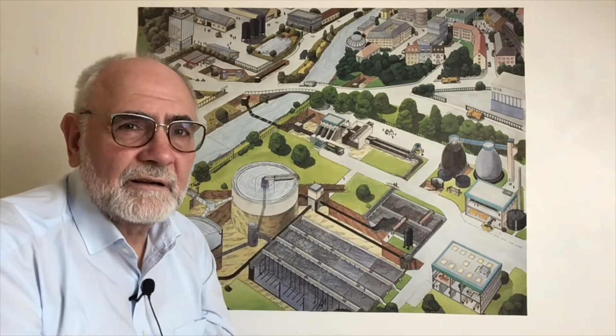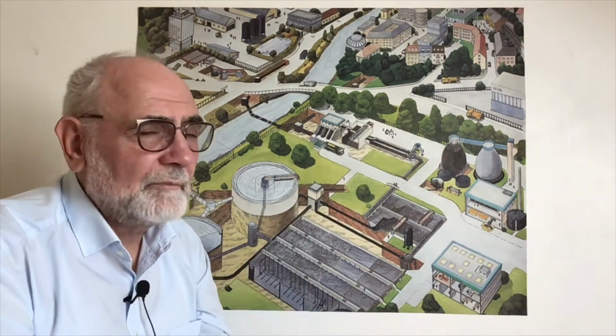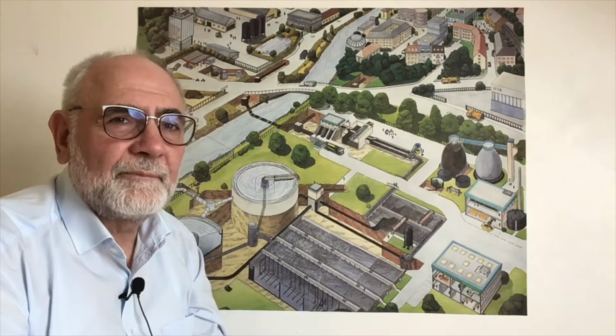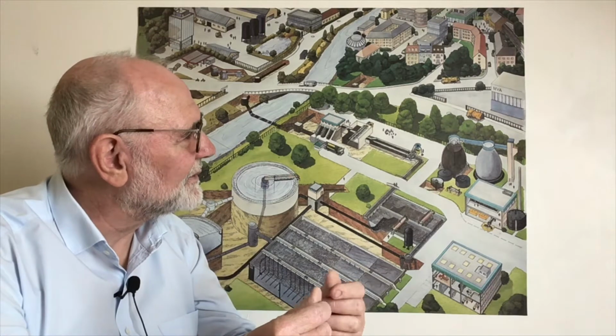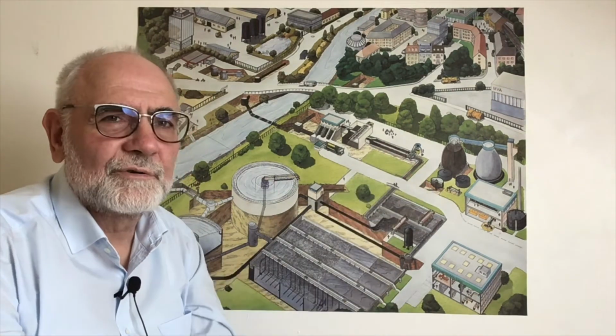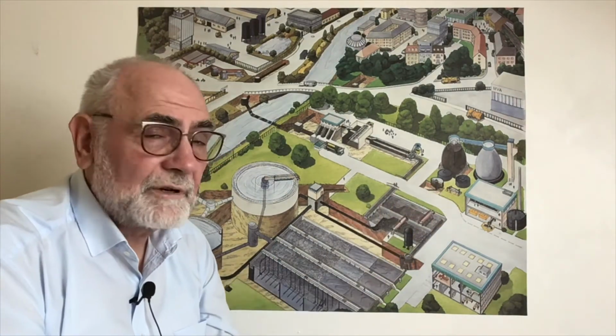Next one is a screen, a solid screen where all the big particles will stay. A finer screen mainly also there, and you put it in the container and then put it to landfill to get rid of it. Next one is a grit chamber, so the velocity gets slower, slower, slower. All the stones and material, gravel goes down, sinks down. All the oil and fat goes up. So you skim the oil and fat, and the stones and gravel you take out and can use later on for road construction.